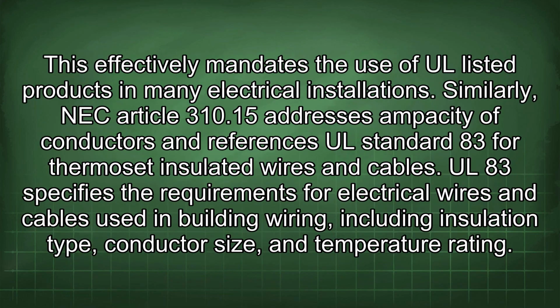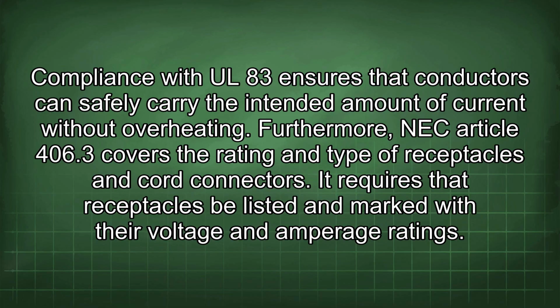This effectively mandates the use of UL-listed products in many electrical installations. Similarly, NEC Article 310.15 addresses ampacity of conductors and references UL Standard 83 for thermoset insulated wires and cables. UL 83 specifies the requirements for electrical wires and cables used in building wiring, including insulation type, conductor size, and temperature rating.